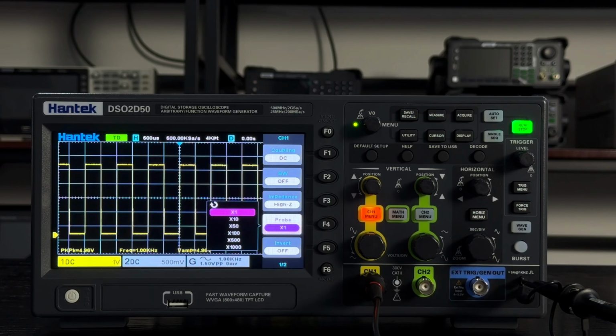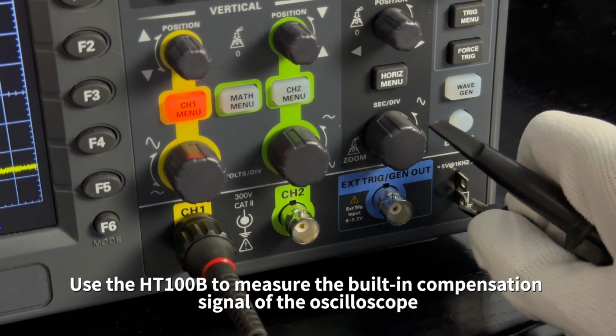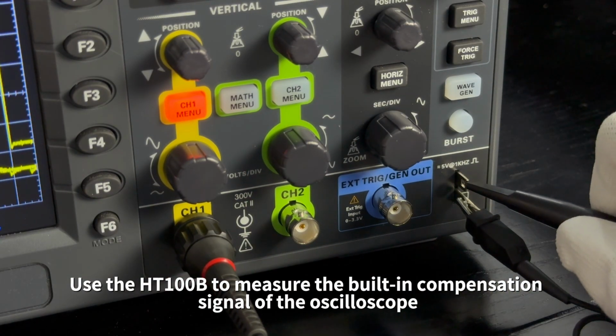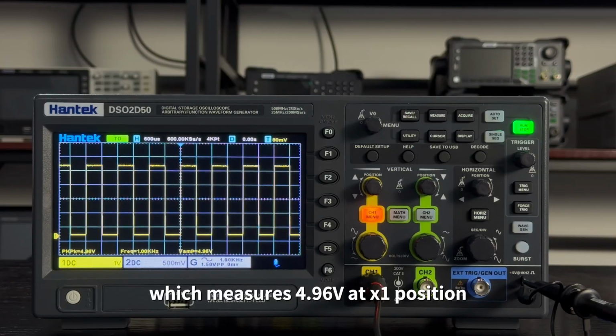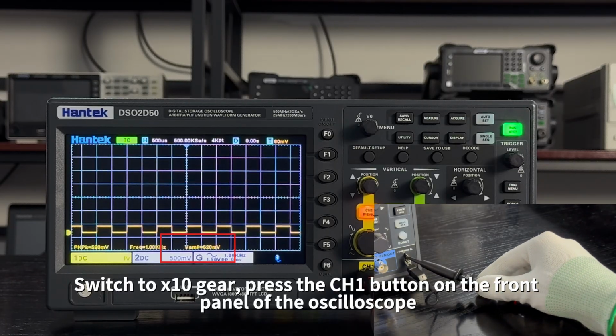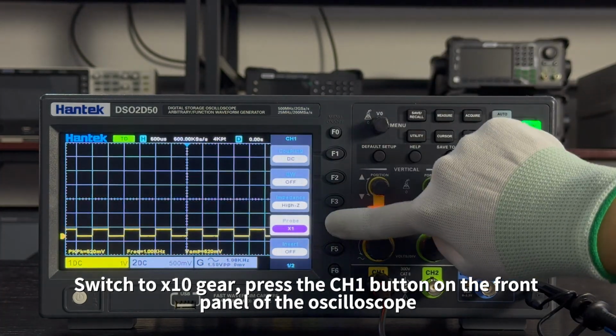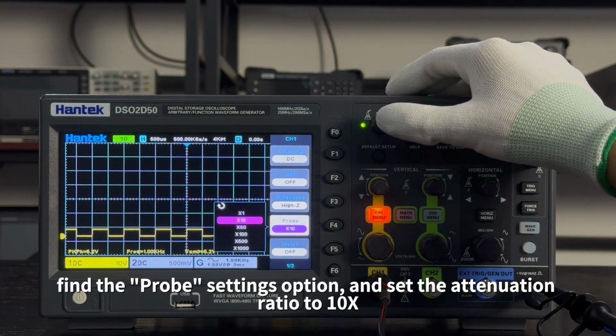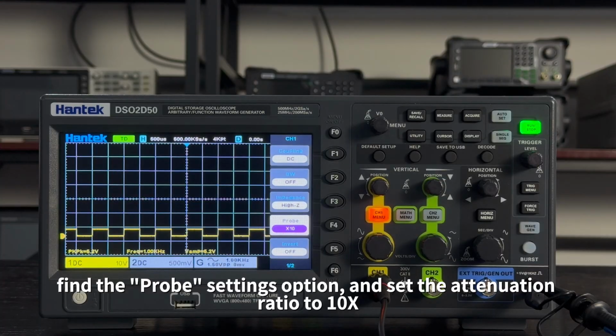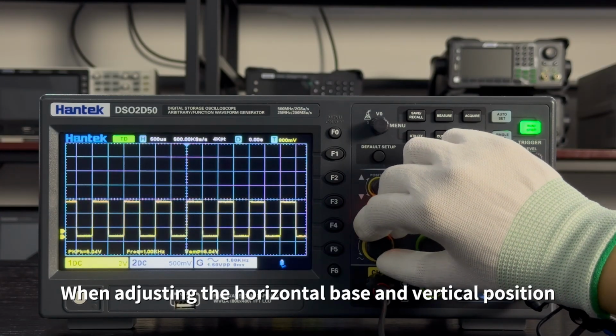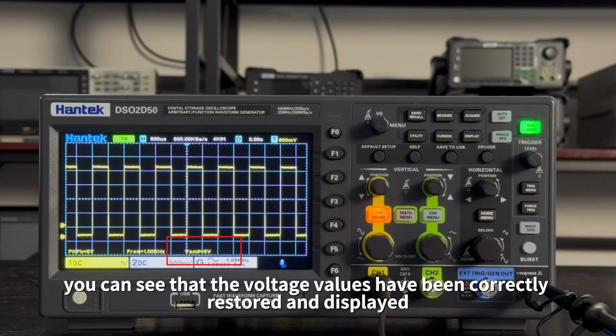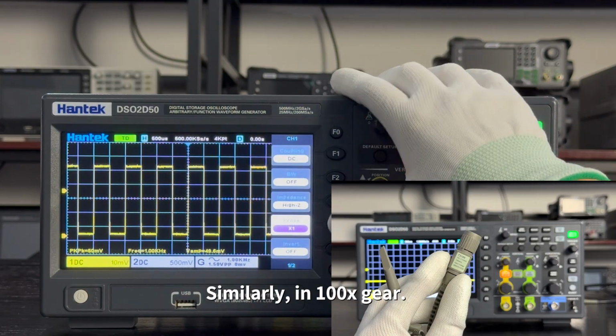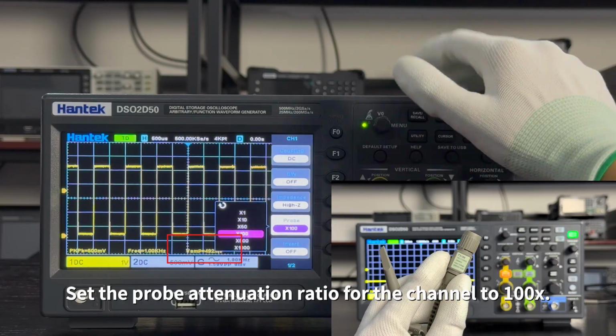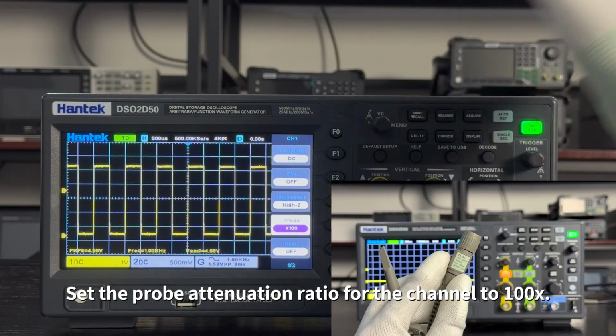display the voltage value. Use the HT100B to measure the built-in compensation signal of the oscilloscope, which measures 4.96 volts at X1 position. Switch to X10 gear, press the CH1 button on the front panel of the oscilloscope, find the probe settings option, and set the attenuation ratio to 10x. When adjusting the horizontal base and vertical position, you can see that the voltage values have been correctly restored and displayed. Similarly, in 100x gear, set the probe attenuation ratio for the channel to 100x.